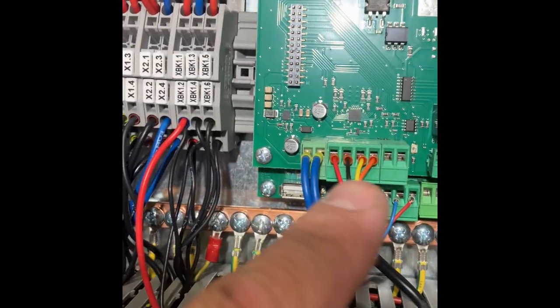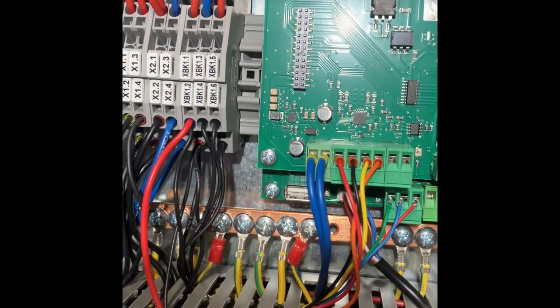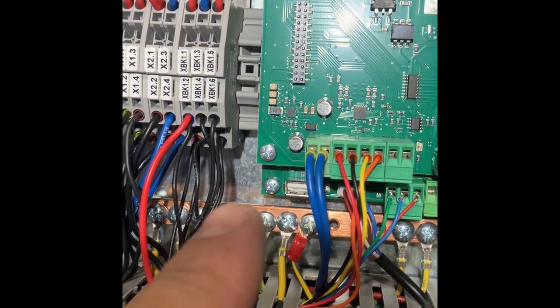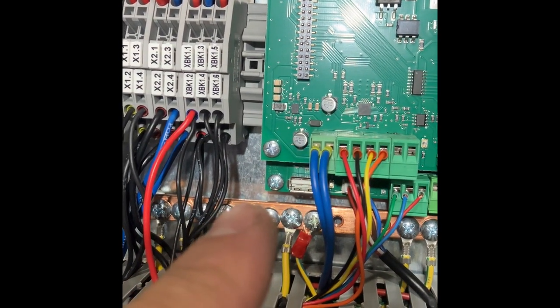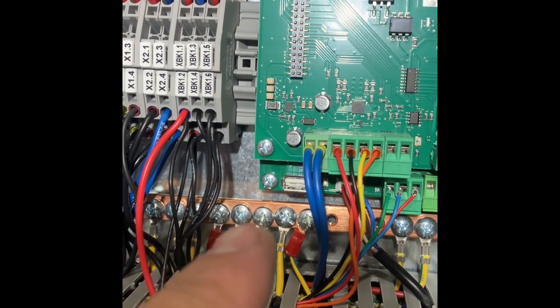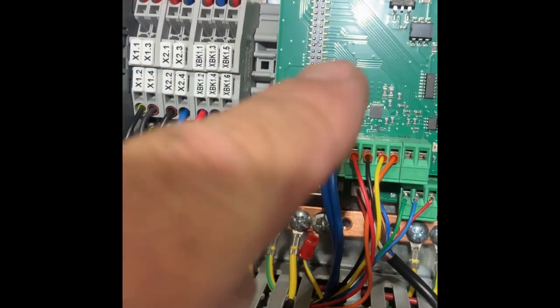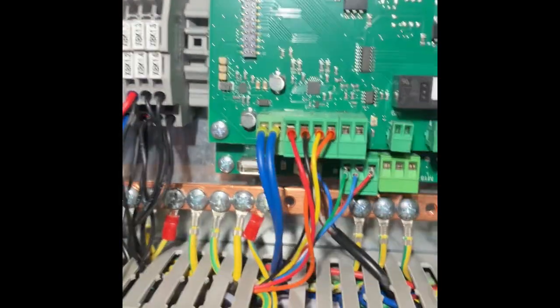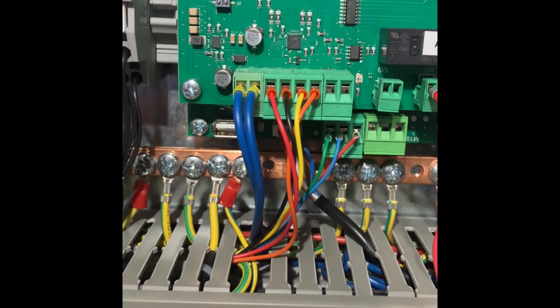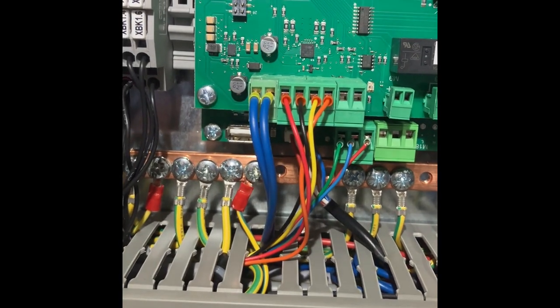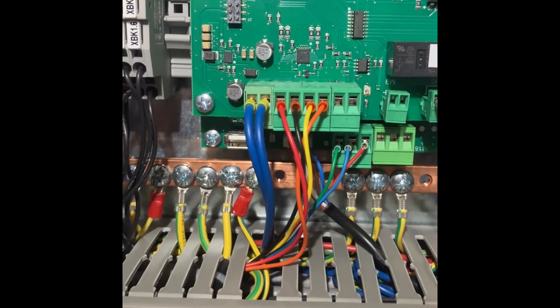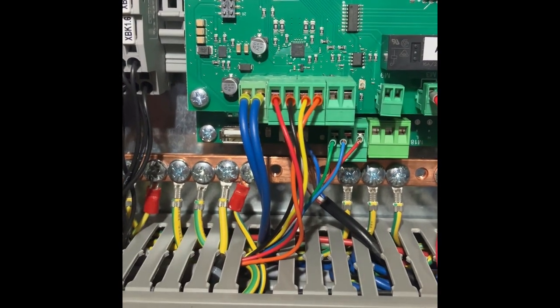Normally a digital input is just a loop. So you might have, say, 24 volts generated here, and whatever it is, your controller or whatever will send that 24 volts out. It will come through a set of contacts and then come back, and it's literally a loop. The Aero on its digital inputs is actually looking for a complete circuit. So it doesn't send a loop out, it just looks for power to come in.